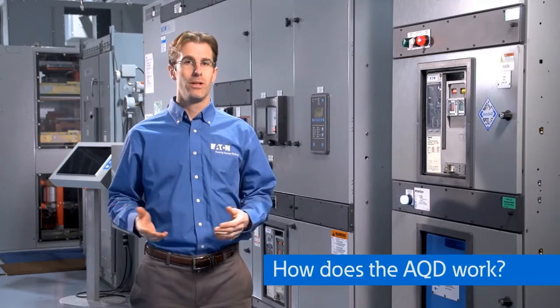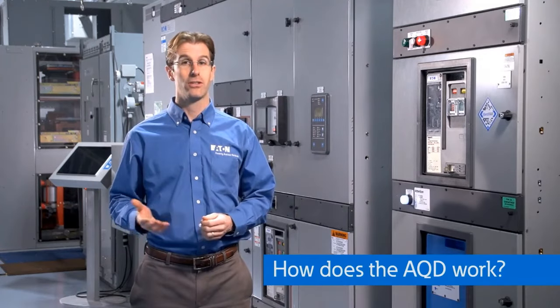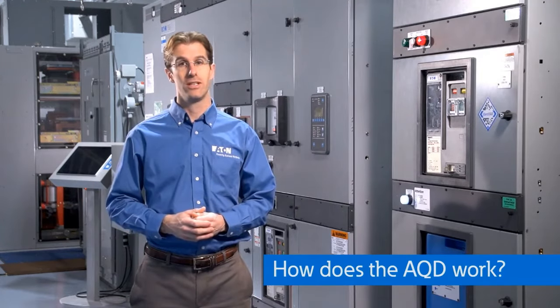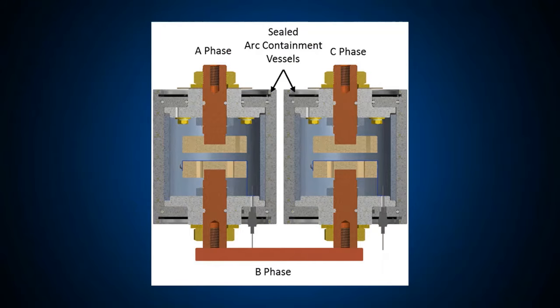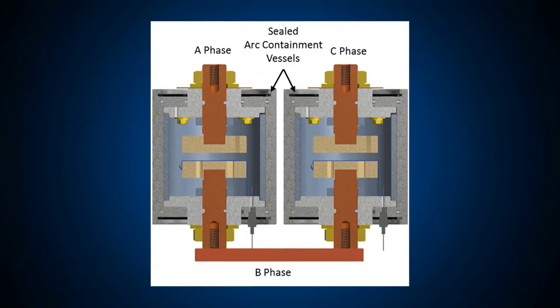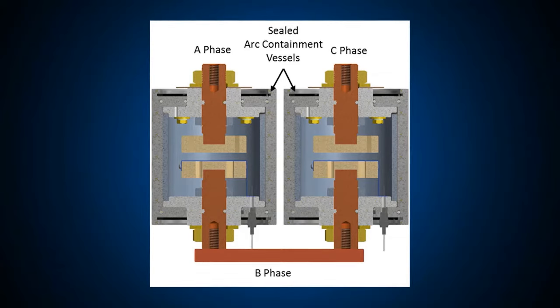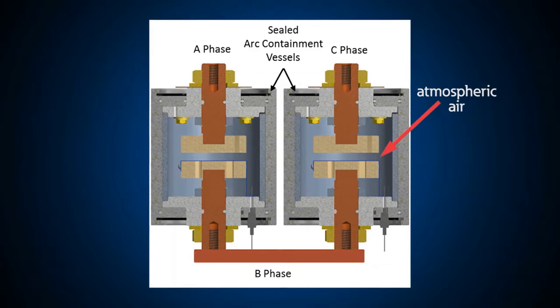By now you must be wondering how the arc quenching device actually works to extinguish an arc flash inside the switchgear. Shown here are the internals of the arc quenching device. As you can see, there are 2 arc containment vessels inside. What's shown here are actually cutaways. Each vessel is about 7 inches tall, about 5 inches in diameter. They look a little like vacuum contactor bottles, but they're not. They're actually filled with atmospheric air because under certain circumstances, we actually want arcing to occur inside these vessels.